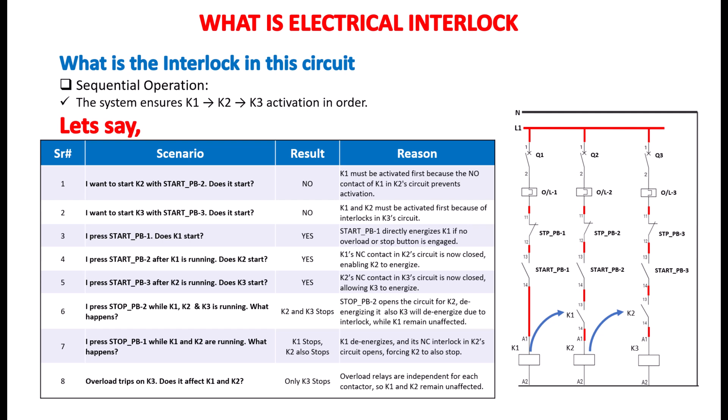Scenario 8. If K3's overload trips, does it affect K1 and K2? Nope, no, only K3 stops. Overload relays are independent for each contactor, so the other circuits continue running without issue.